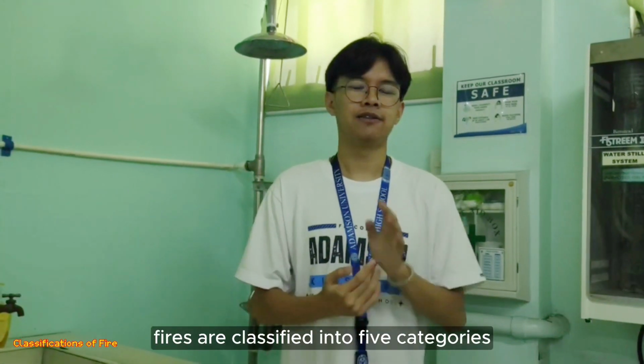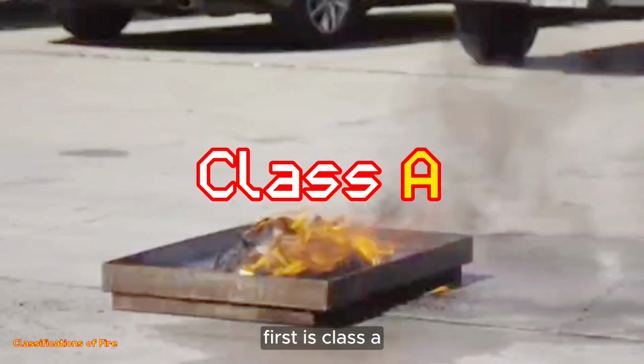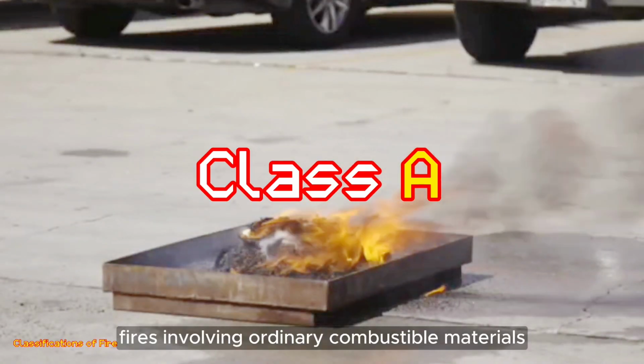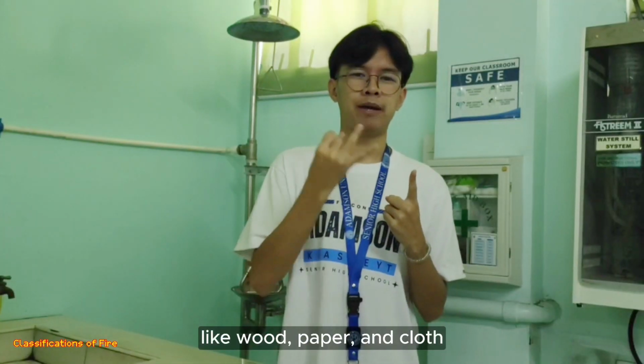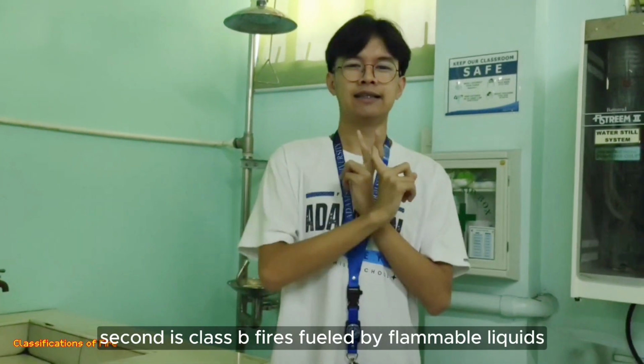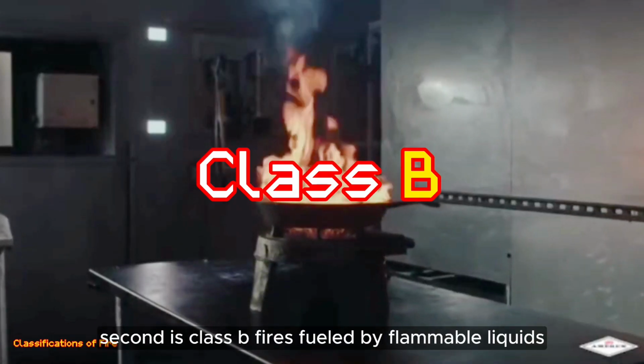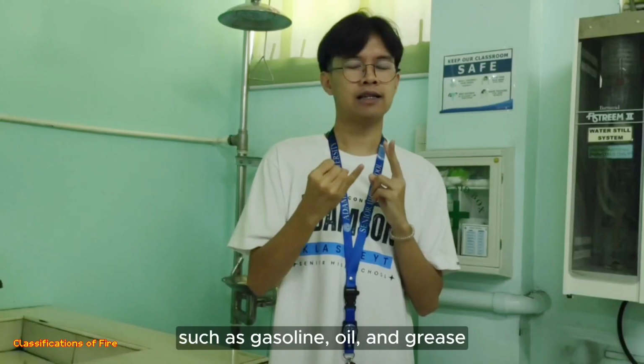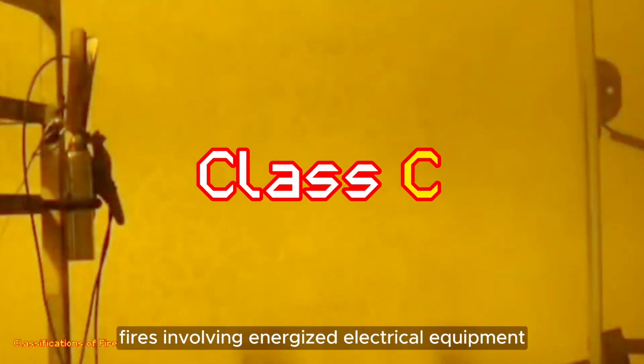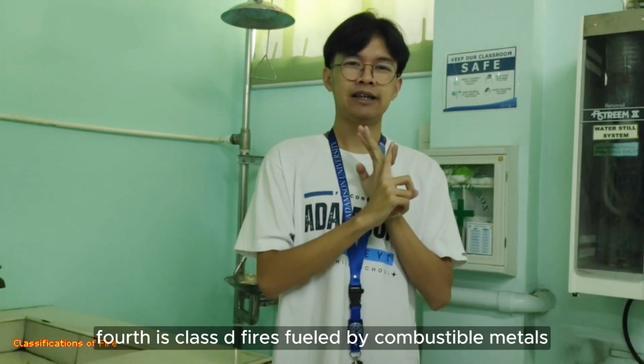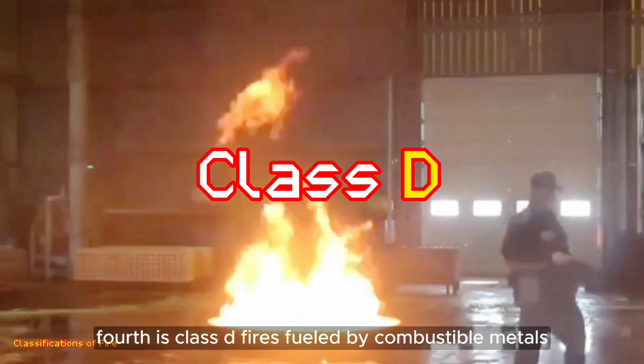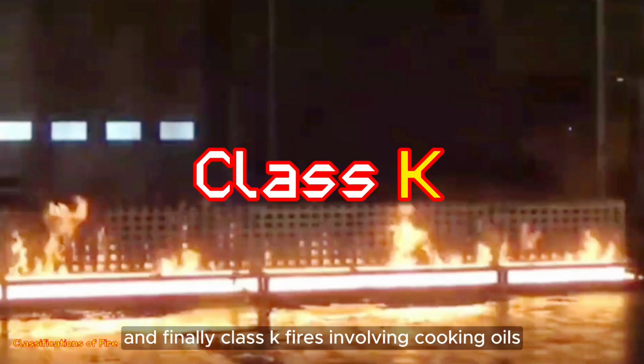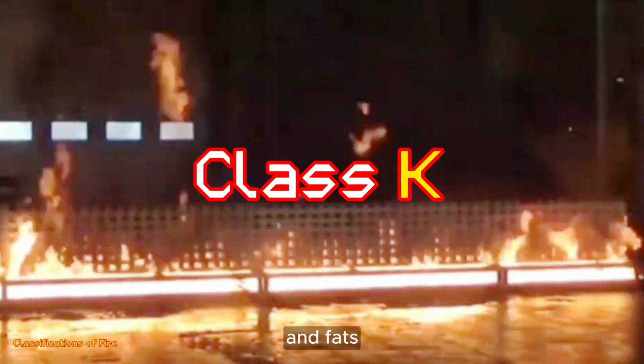Fires are classified into 5 categories. First is Class A. Fires involving ordinary combustible materials like wood, paper, and cloth. Second is Class B. Fires fueled by flammable liquids such as gasoline, oil, and grease. Third is Class C. Fires involving energized electrical equipment. Fourth is Class D. Fires fueled by combustible metals. And finally, Class K. Fires involving cooking oils and fats.